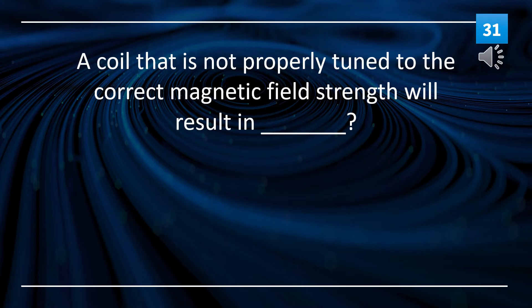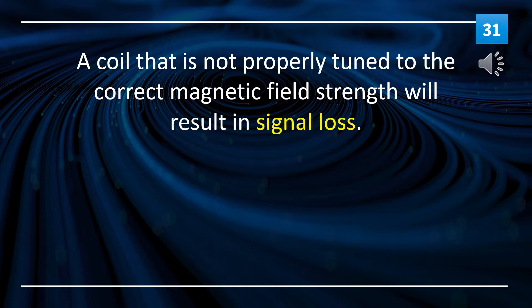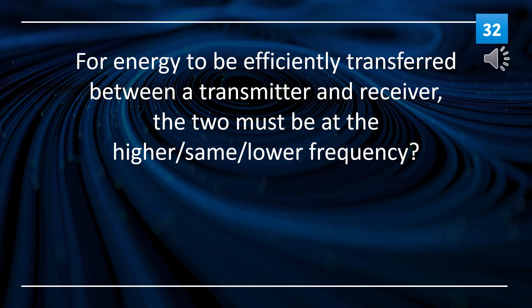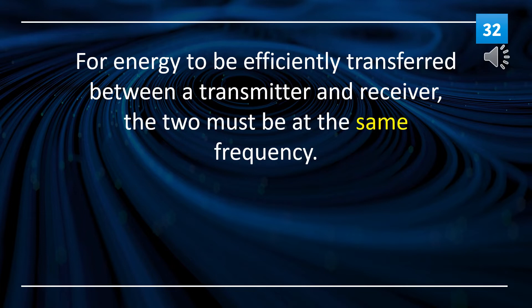A coil that is not properly tuned to the correct magnetic field strength will result in signal loss. For energy to be efficiently transferred between a transmitter and receiver, the two must be at the same frequency.